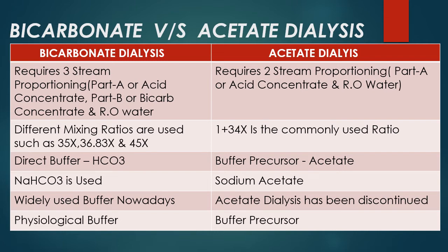Regarding buffer nature: bicarbonate is a direct buffer. Acetate, on the other hand, is a precursor — meaning acetate is first metabolized in the liver to generate bicarbonate ions in an equimolar ratio. In the bicarbonate concentrate, the main component is sodium bicarbonate (NaHCO3), also known as sodium hydrogen carbonate. For acetate dialysis, the concentrate contains sodium acetate or sodium diacetate.